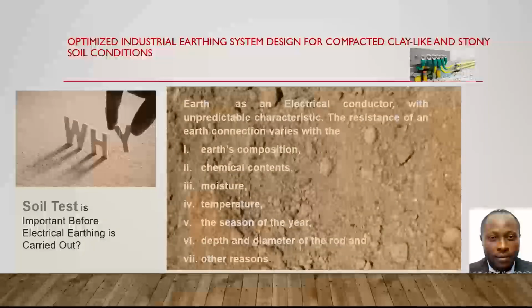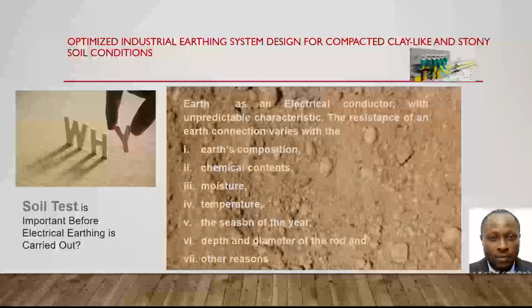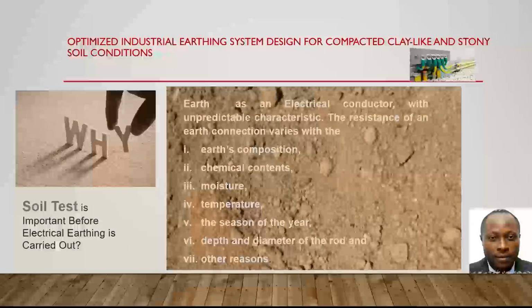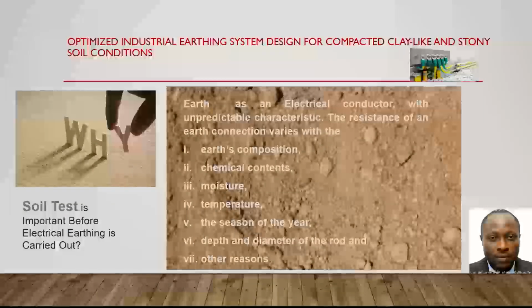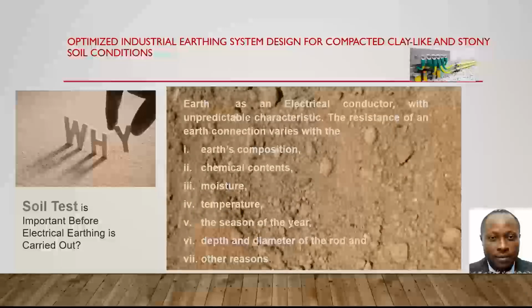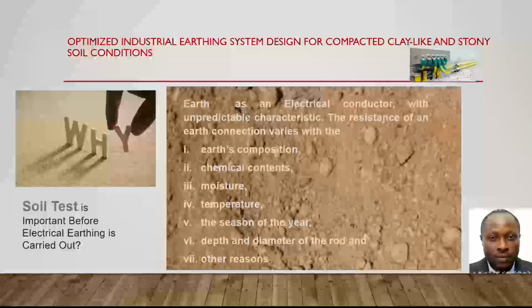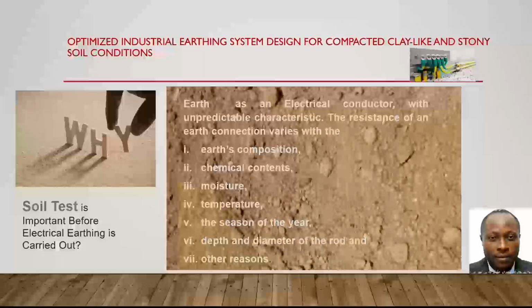Why earth? Earth is an electrical conductor with unpredictable characteristics. The resistance of an earth connection varies, because earth has a lot of composition. The chemical content differs, if you go to one geographical area, the chemicals, minerals, and compounds in the soil are different from another area. The moisture content of the soil is not the same, temperature is not the same, and the season of the year also changes a lot of things concerning the soil.